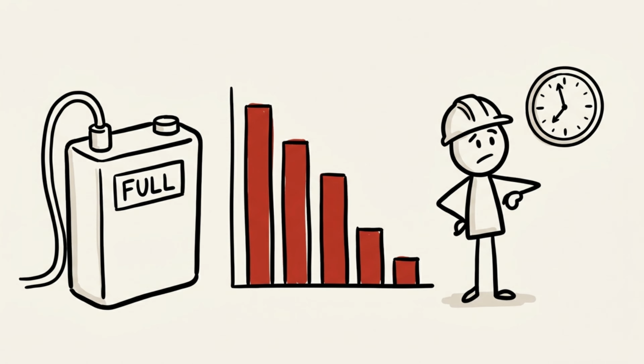Failure 3. The runtime mirage. Symptom: the battery reads full on the display and still dies hours earlier than expected. Actual cause: the original sizing used raw battery capacity instead of compounding the real losses.